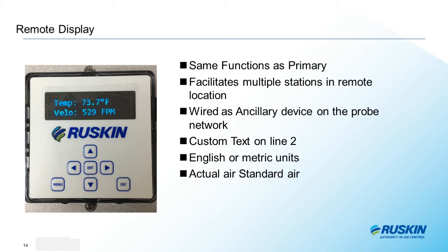However, if a wire can be run from the primary or any ancillary probe to the remote display, then the wired remote display will save a few dollars. With multiple air measurement stations installed in a building, any number of wired or wireless remote displays can be located in one convenient location, making it easier to see dynamically each air handler in the system and all the air measurements. The benefit of this is that we are no longer tethered to the air measurement station's location. We can put the remote primary controller up to 500 feet away or use the wireless remote up to 200 feet away. This, again, facilitates multiple air measurement stations in the building in one convenient location.